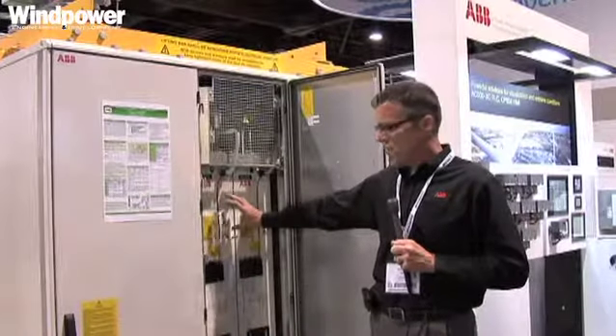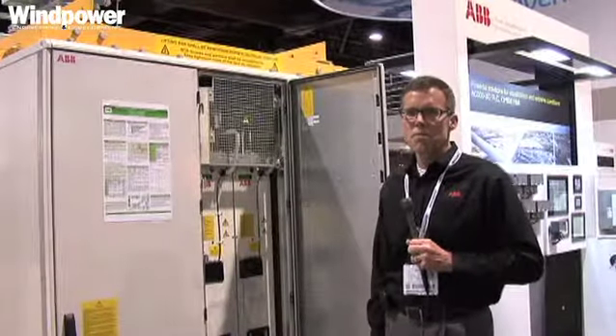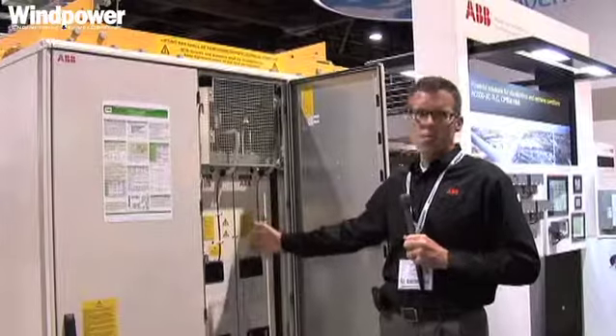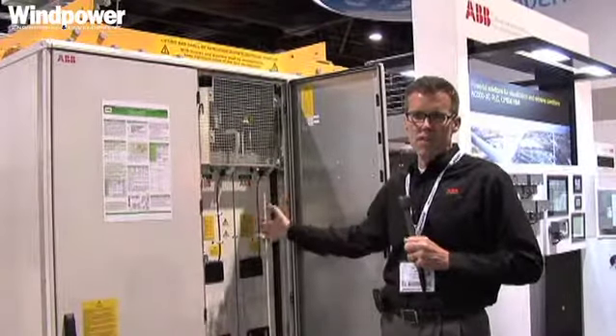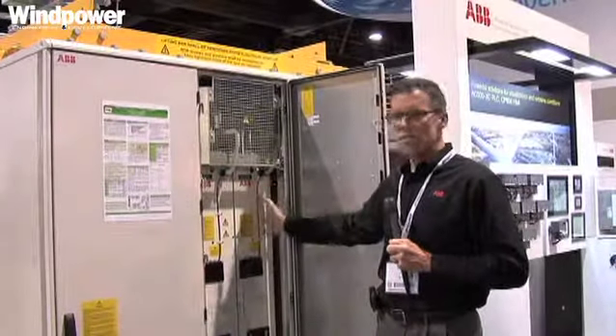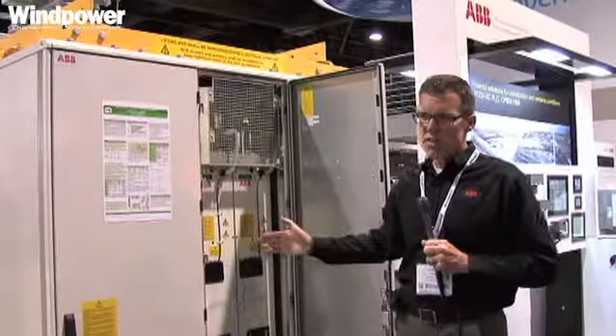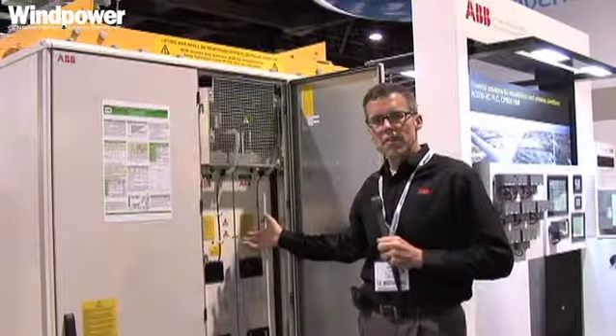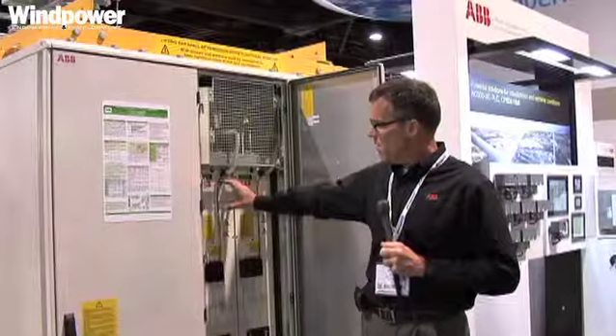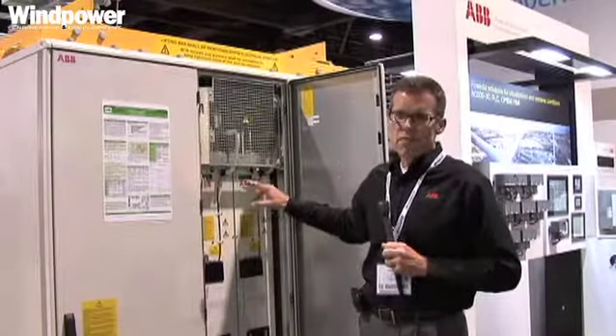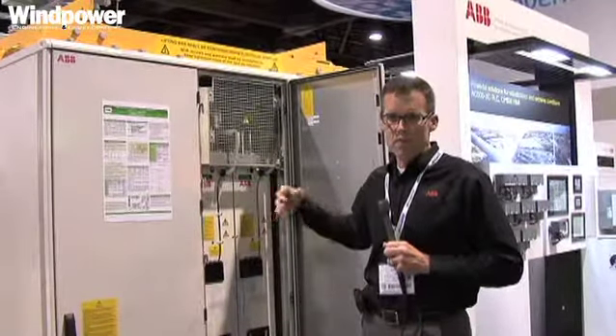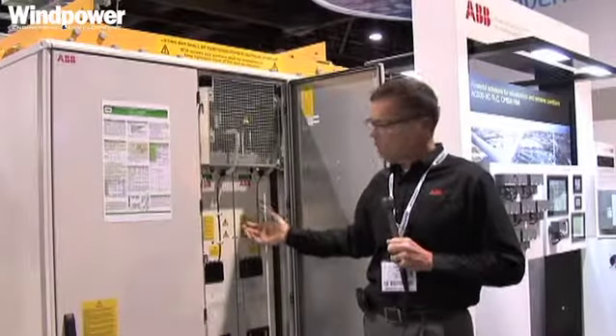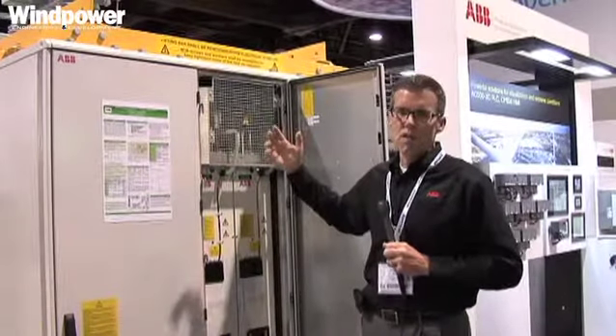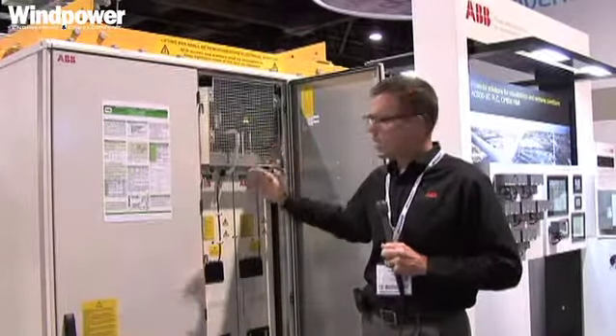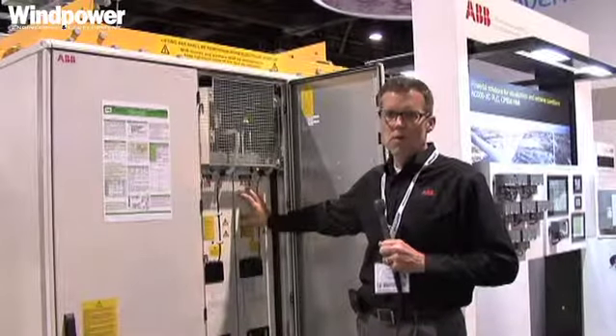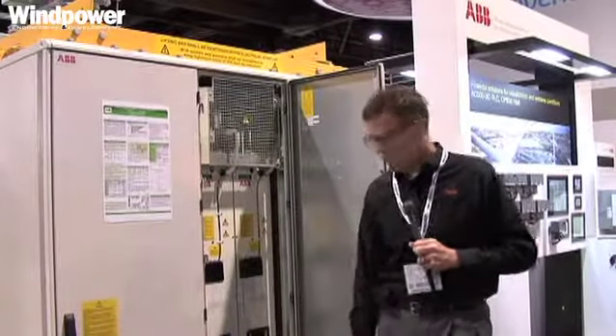Each of these three-phase modules is about 650 kilowatts per module. With the modular approach, we can scale up to the size of the turbine at hand by adding modules in parallel. From a reliability standpoint, if one module fails, you can quickly replace it by removing a few bolts, or if you don't have a spare module on board, you can simply isolate that module electrically by removing the fuses and run the turbine at a reduced power load until you can get a spare part on hand.